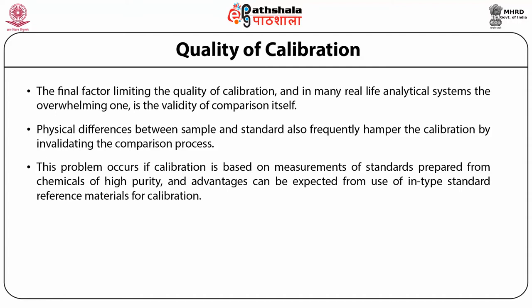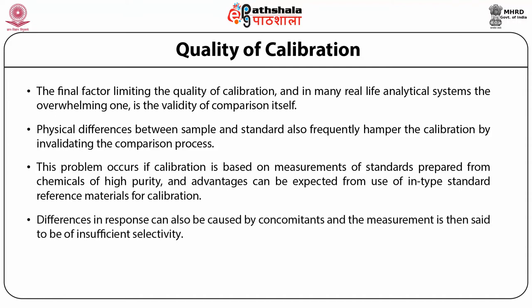In calibrating an instrument, one must be reasonably sure that the instrument will respond to the measurement in the standard in the same way it does to the measurement in a different environment — the unknown. The physical differences between sample and standard also frequently hamper the calibration while invalidating the comparison process. Among the physical properties that need to be identical in standards and unknowns are temperature, pressure, viscosity, turbidity, particle size, surface roughness, and thickness. Differences in response can also be caused by concomitant species — the measurement is then said to be of insufficient selectivity.